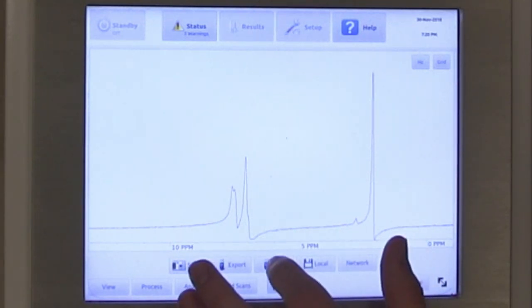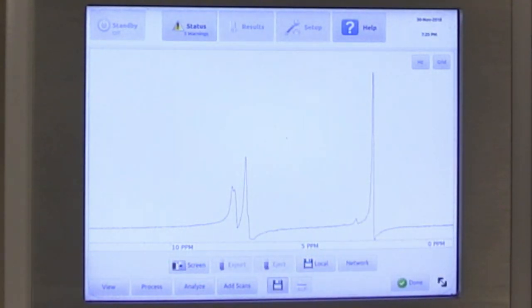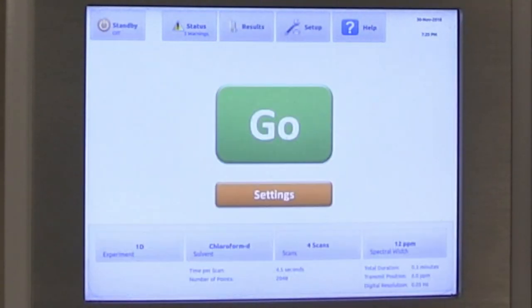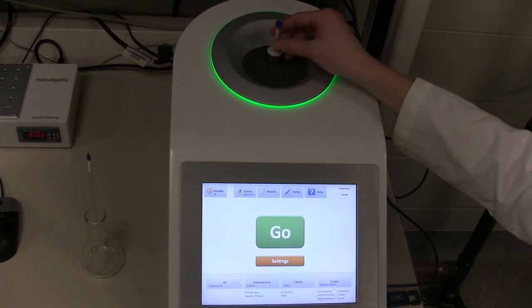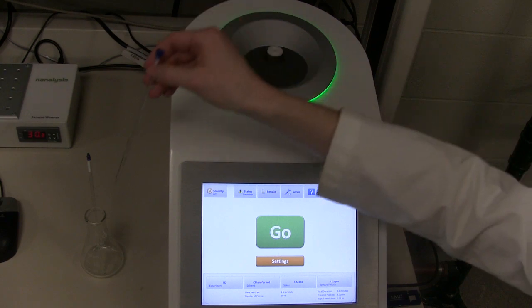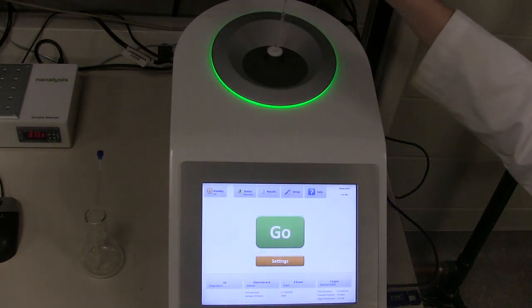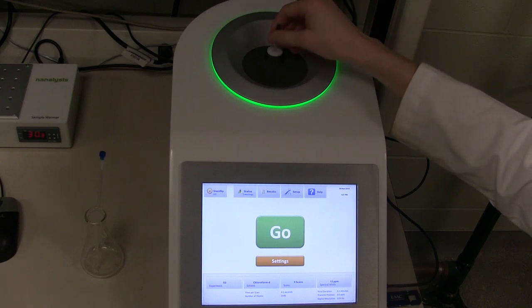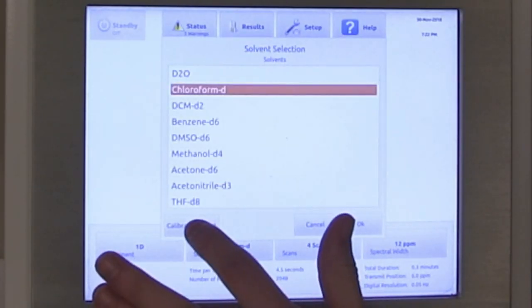Eject the USB key. Press Done in the right hand lower corner. Remove the USB key. The instrument then needs to be recalibrated to the standard. Remove the sample NMR tube and place the standard tube inside. Press Solvent and then Calibrate.